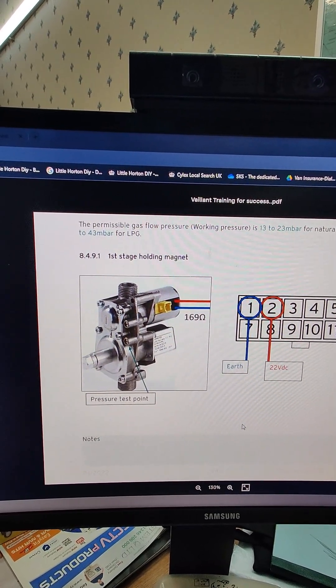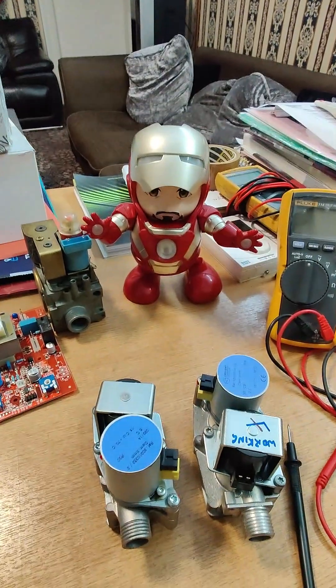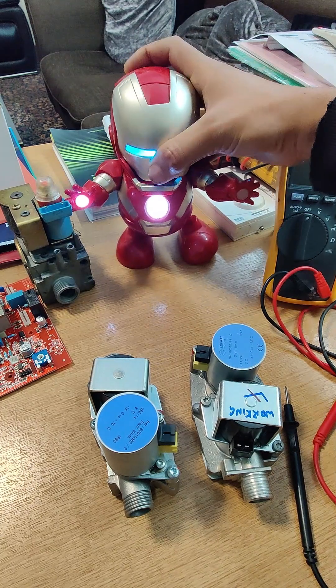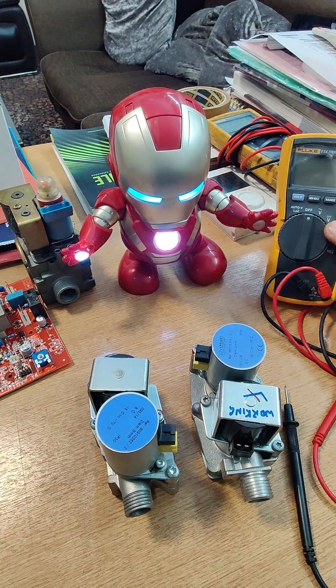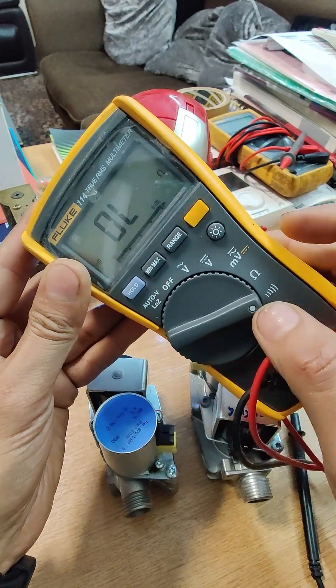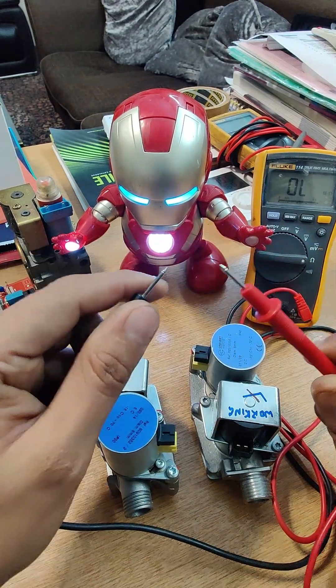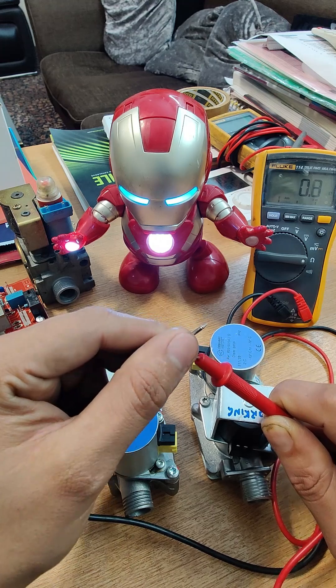Let's carry out the first test, which is on the first stage holding magnet — we're expecting around 169 ohms resistance. Let's set up the camera and get some light. Let's set our multimeter — we need it on resistance setting, not on the buzzer setting we use most of the time for continuity. There is always some resistance within the cables; if you want to know what it is, just touch them together — it's around 0.8 ohms, which is negligible.